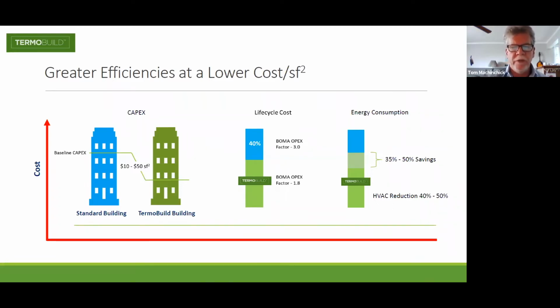With regard to life cycle costs, integrated ventilation design is 40% less expensive over the life of a building. You'll notice in the center graphic here, we have a BOMA OPEX factor of 3.0 for a standard building. And what that means is if your building costs $100 million, over the life of the building, you'll spend $300 million on operating expenses. With an integrated ventilation design, the BOMA OPEX factor is 1.8, which is 40% less than a standard building. That means that a $100 million building will have $180 million over the life of the building.